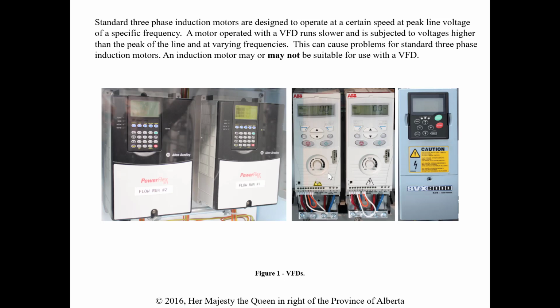So I'll go through this again the best way I can, but knowing that you could easily stop this at any time and read what I have on there. So I'll try not to read verbatim over and over here. The big thing to have an understanding of with VFDs is that there's certain motors that will not work with VFDs and they could get damaged. And they talk about how or why that's an issue throughout this module. Not to mention the cabling as well. Okay, so there's very specific motors and cabling that we should be using with a VFD.